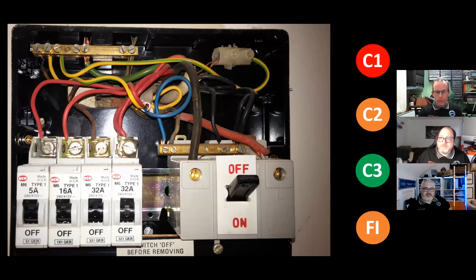Yeah, that's a classic MEM 3871 board. What have we got? We've got VIR there. We've got connectors on the CPCs. I don't know why, they probably just couldn't extend over to the earth bar. It just looks like there's been poor alterations and additions there. Whether that VIR even has a CPC. In fact, you can see on the neutral, Dave, if you just look where the twin and earth is, the red, yellow and blue three core they've used, you can see there's exposed strands of that VIR.